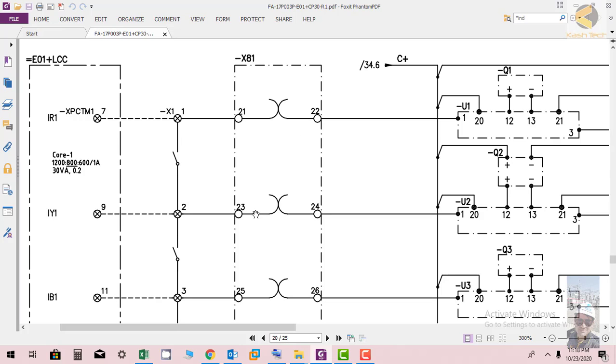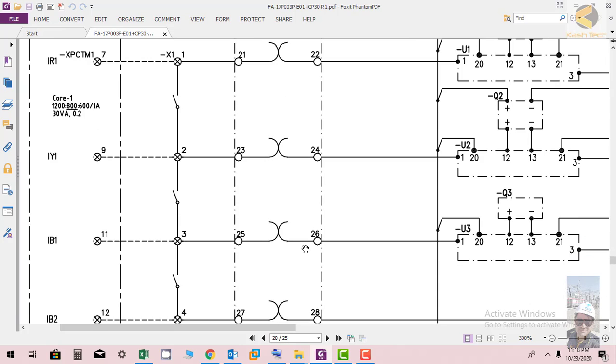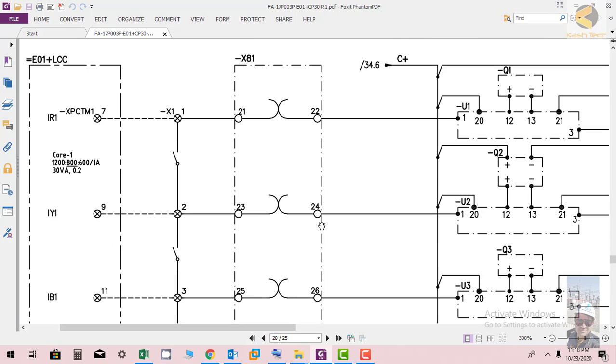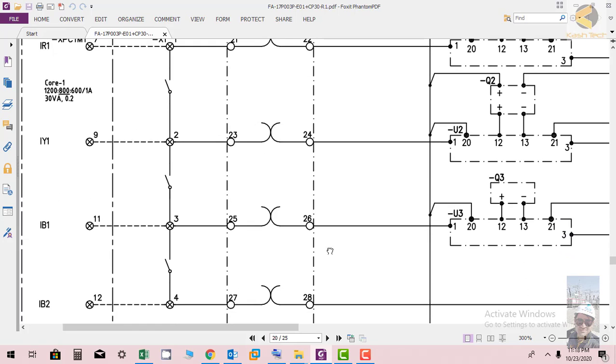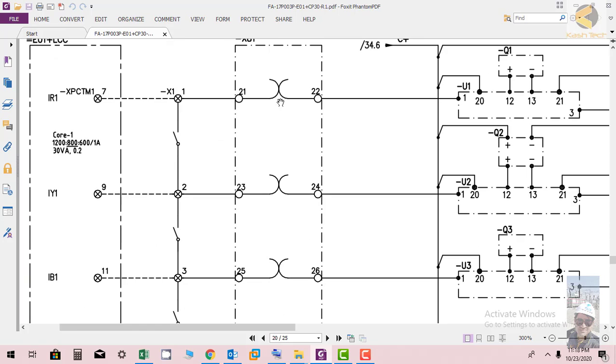It will isolate 21 and 22, 23, 24, 25, 26, 27, 28 and you can connect your secondary injection kit at the even side which is 22, 24, 26 and 28. The odd side will be isolated which is connected to the field side.